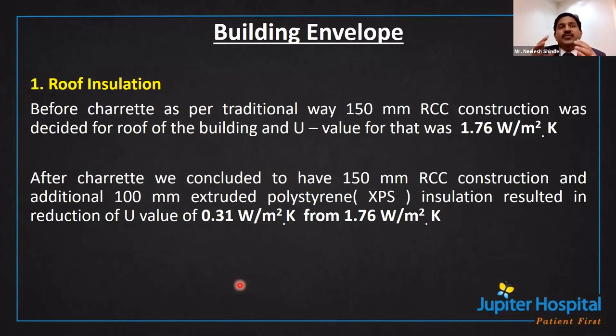In HVAC, there is something called a building envelope. Every building has some terrace. Normally, before the charrette, in our Thane hospital, we did it the traditional way - using 6 inches RCC construction on the roof of the building. The U value was 1.76 watts per square meter dot Kelvin.